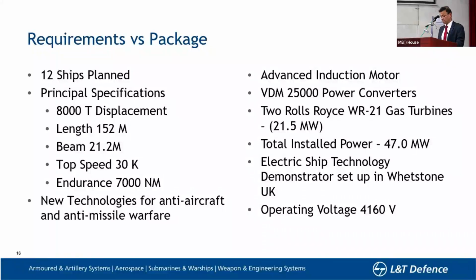Next comes the prime mover. On the Type 45 destroyer, the IEP configuration has two specially developed WR21 gas turbines of 21.5 megawatt, besides two 2-megawatt diesel alternators feeding into a common bus bar. As we know, diesel engines cannot meet the powering requirement of destroyers, and simple gas turbines have a major drawback of poor part-load efficiency.